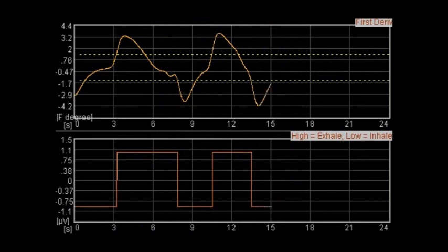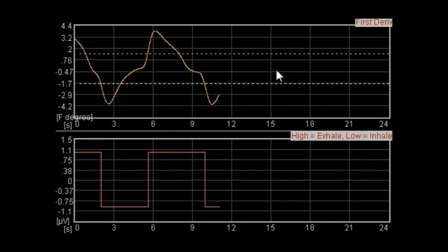The key to reliable breath measurement is detection of the breath's turning points, or the beginnings of the inhalation and exhalation. This chart shows you what well-calibrated breathing looks like. These two dotted yellow lines should be positioned something like this. Neither is too close to the center of the graph or to the outer points.